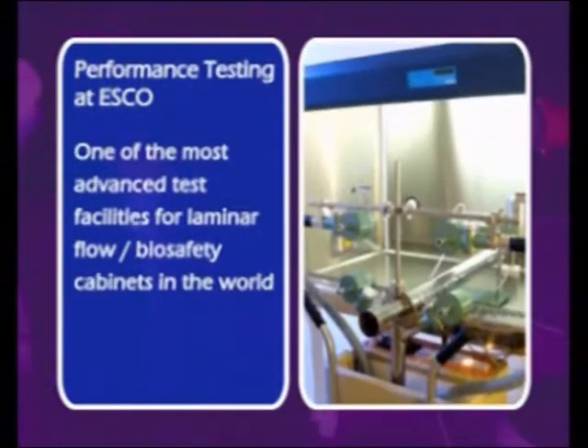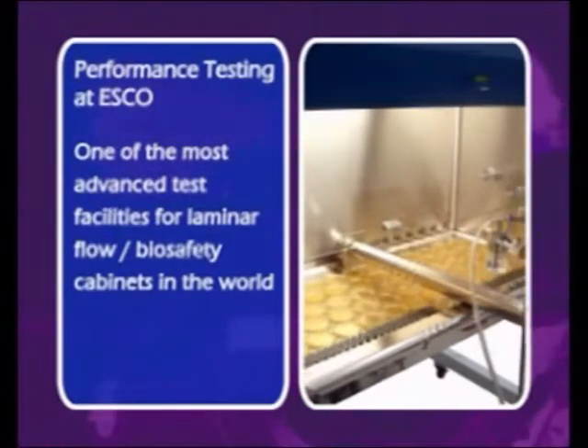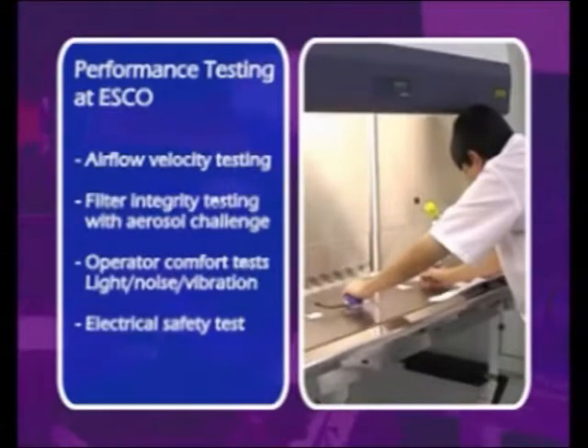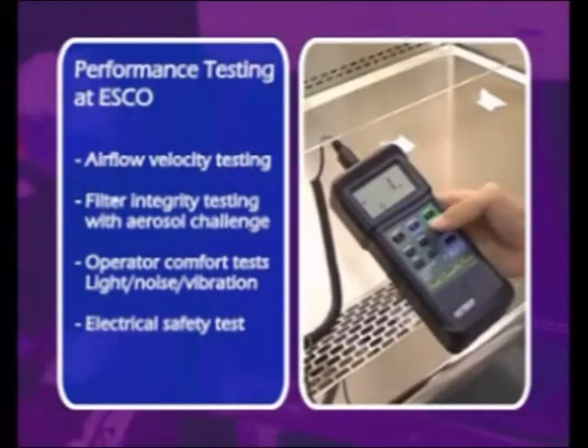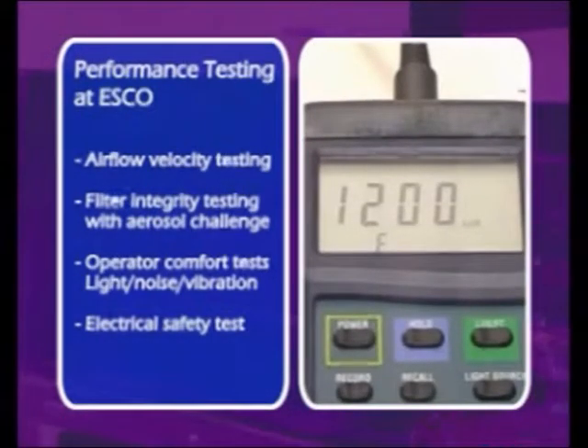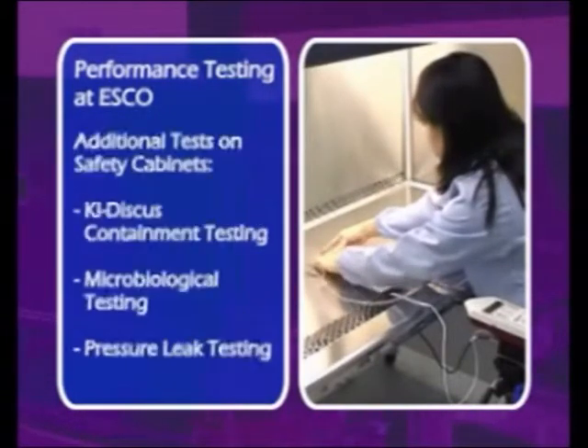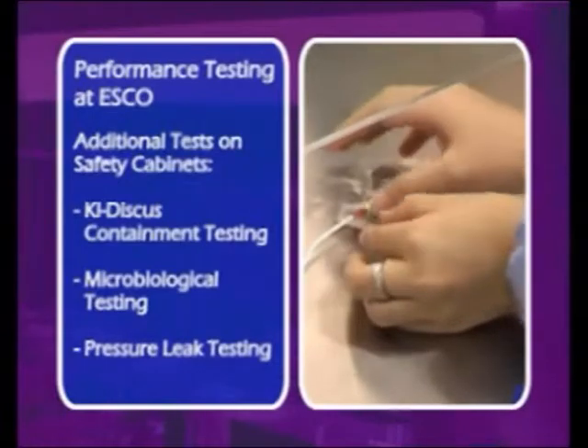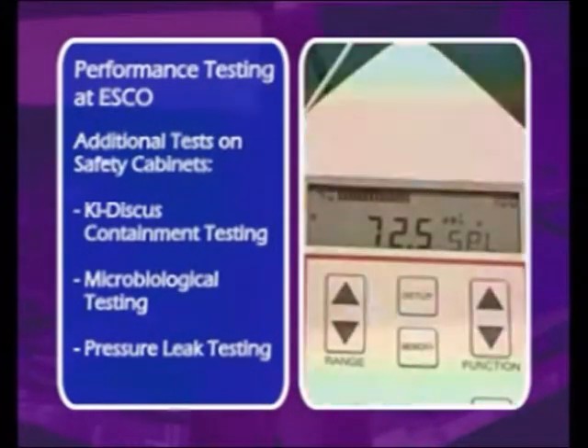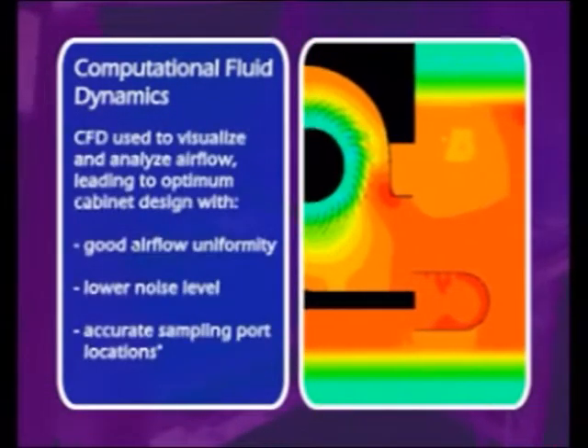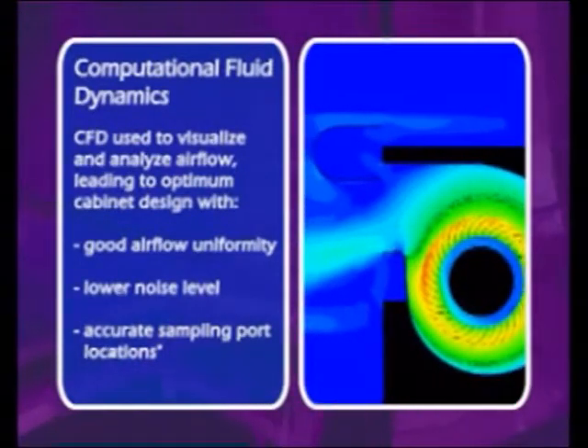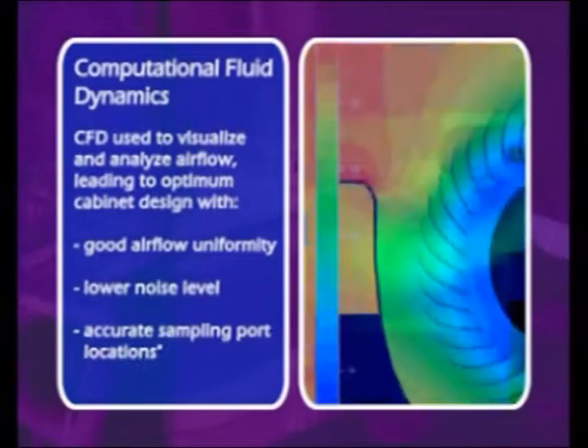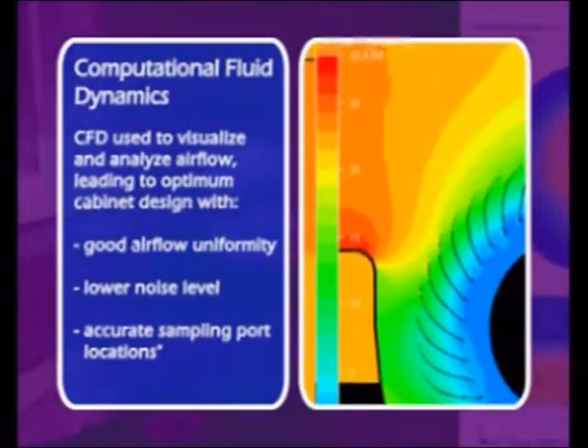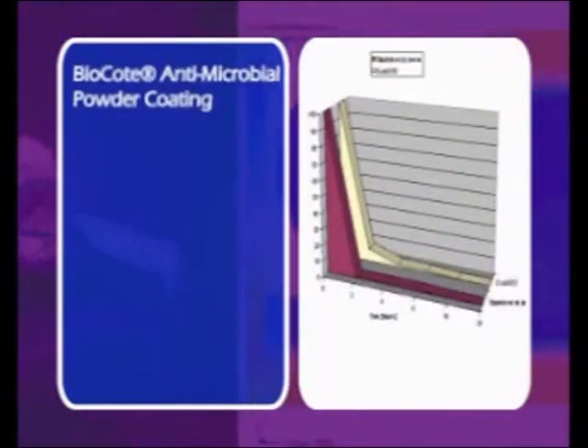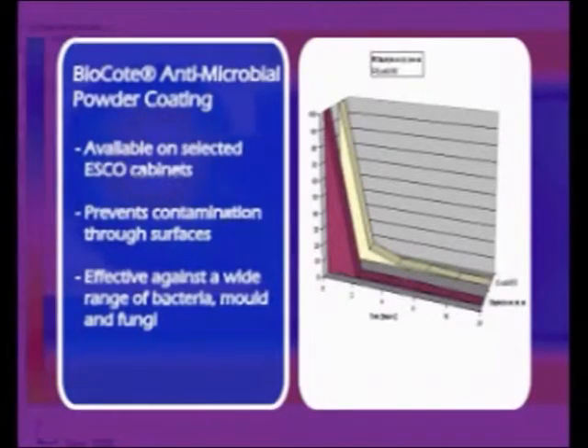Performance testing conducted on all produced ESCO products include tests according to relevant international standards. These may include airflow velocity testing, aerosol challenging of filters, operator comfort tests, and electrical safety tests. Additional tests are performed on ESCO products, including the KI discus containment testing and microbiological testing. Computational fluid dynamics software is used to visualize and analyze airflow within the cabinet based on whichever optimum cabinet design is produced. ESCO employs BioCote antimicrobial powder coating on its lab culture range of Class II biosafety cabinets, which ensures contaminant-free surfaces.